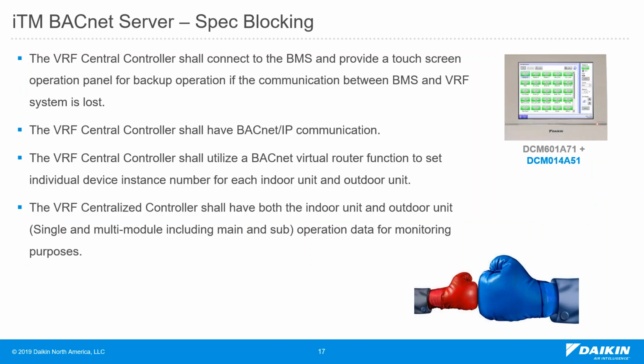So how do you use the ITM BACnet server as a spec blocker? If you use similar sentences, like "VRF central control shall connect to the BMS and provide a touchscreen operation panel for backup operation if the communication between the BMS and the VRF system is lost," that could be a spec blocker. Also, if they put something like "VRF control shall utilize BACnet virtual routing function," which nobody else has, "to set an individual device instance number for each indoor unit and outdoor unit," that's also considered a very good spec blocker. The same goes for providing both indoor unit and outdoor unit, single and multi module, main and sub operation data. Those are different ways the engineer can do spec blocking against competitors.